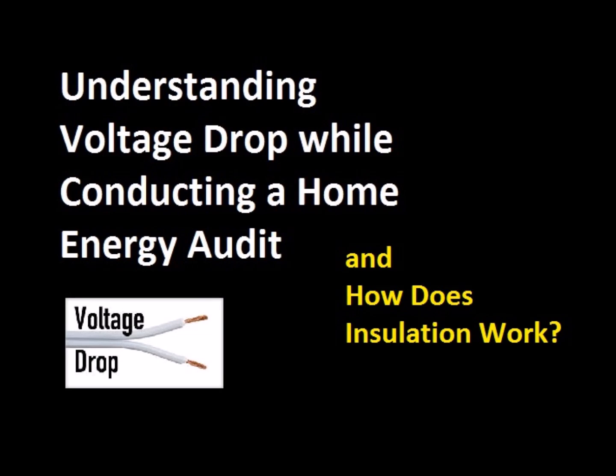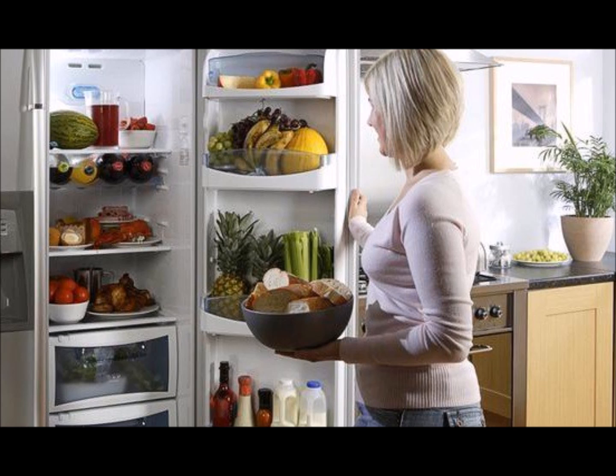Next, we talk about voltage drop. When conducting an energy audit, be sure to test the refrigerator circuit for any voltage drop. Find the electrical circuit associated with the refrigerator. Check it using a meter that puts a 15 amp load on the circuit for a short period of time and measures the voltage drop on it.